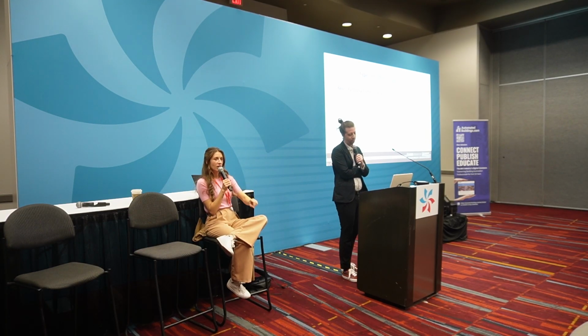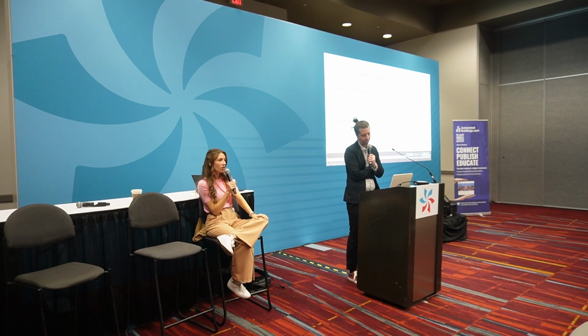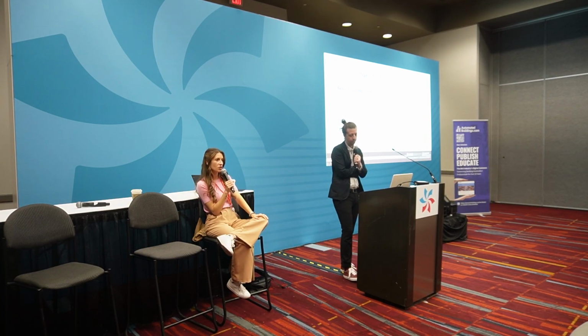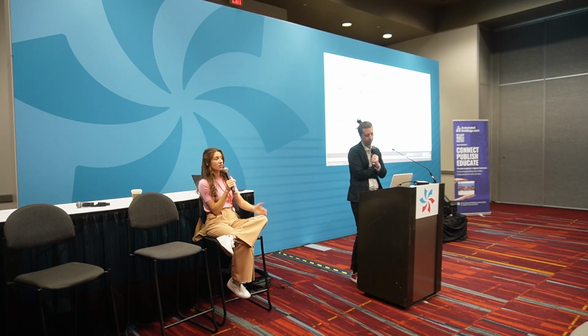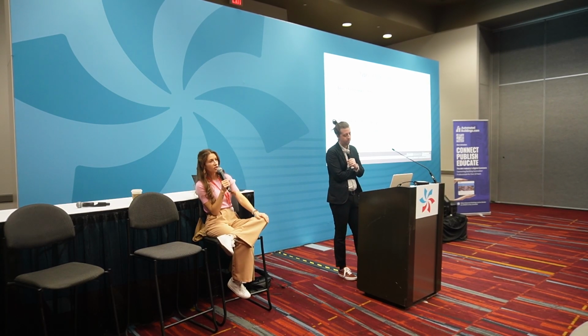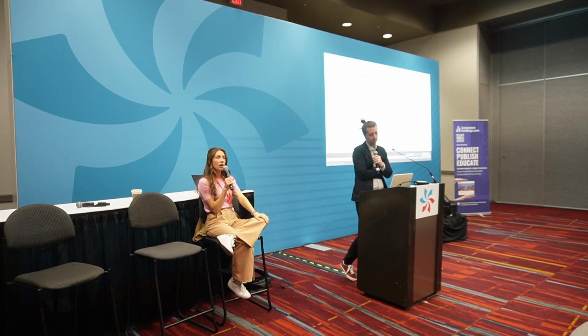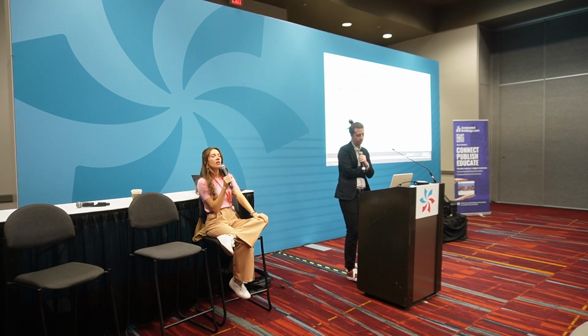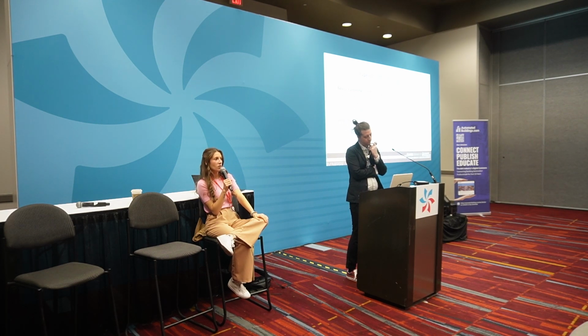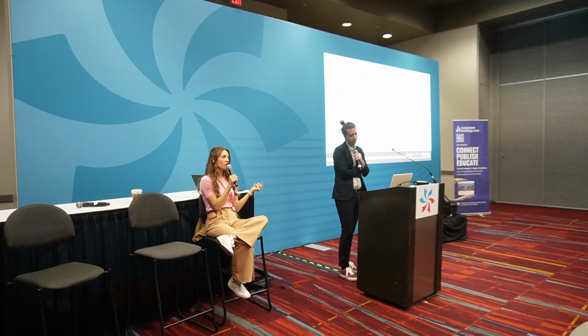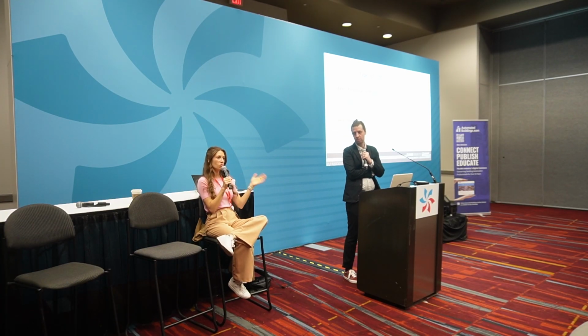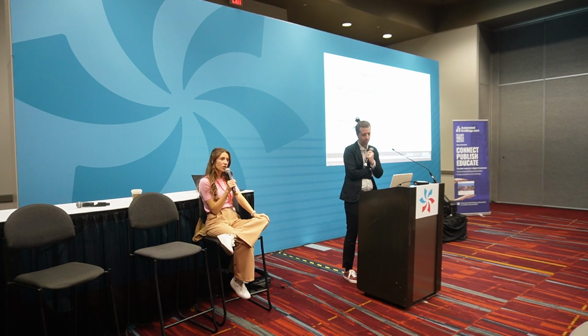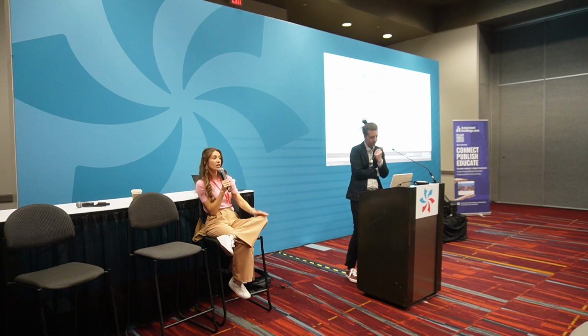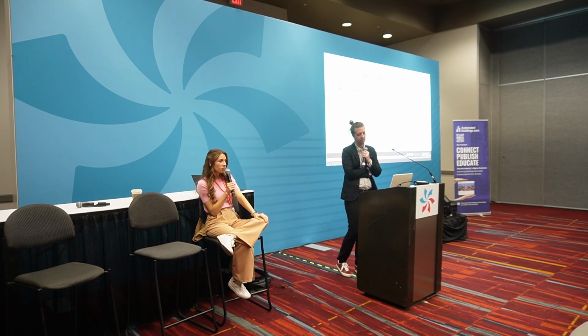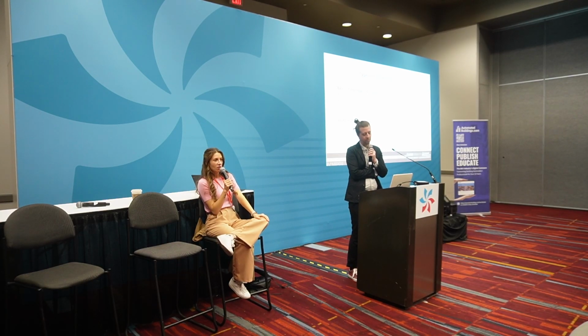So building owners, or anyone doing the projects — what I've found is you often have to specifically spec performance commissioning in your RFQ, or specifically ask for it. This client who asked us to be a commissioning authority had no idea there wasn't going to be any commissioning. The reason she engaged us is because on her last project, where they installed a big air-to-water heat pump in a hydronic loop in a school, it took an extra year because the piping was backwards, some of the valves weren't opening, one side of the school didn't get cooling, and the sequences weren't working. We were supposed to do work on it, and it was like, oh, actually it's not ready yet. For an entire year she was chasing down the contractor, saying, this doesn't work, you're not allowed to leave, come back to my site. She's like, this isn't what I should be doing. So that's where we come in — doing that accountability, managing the commissioning.